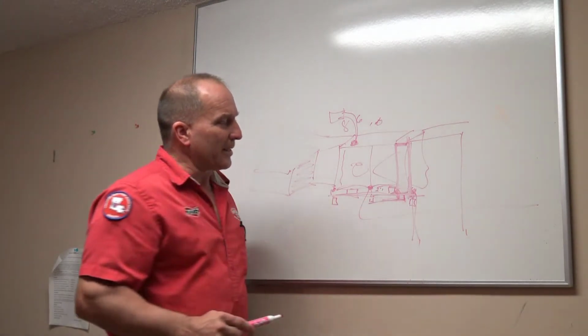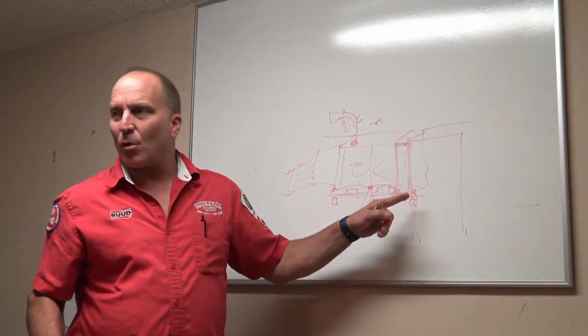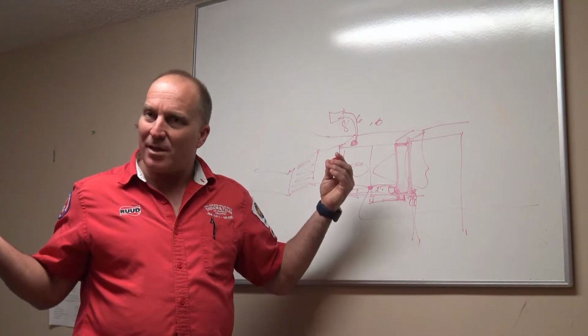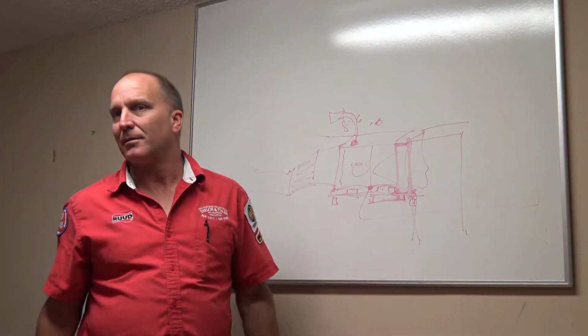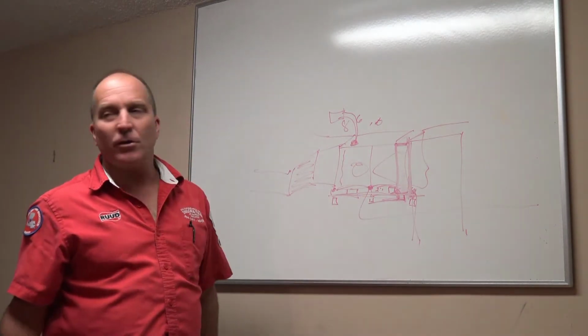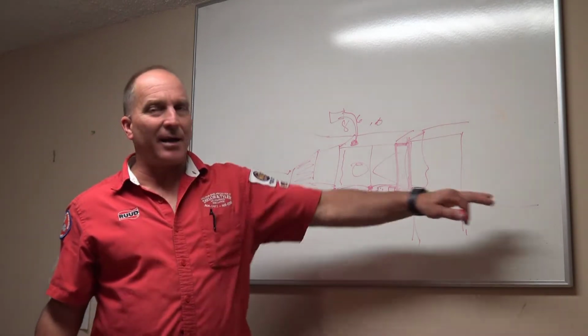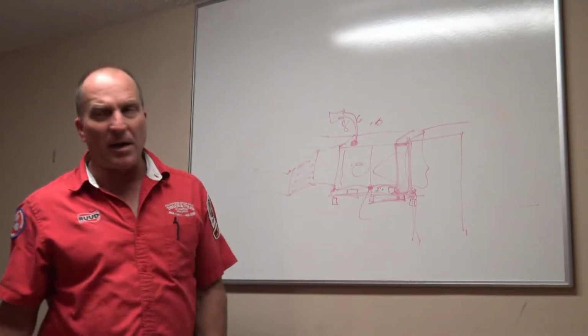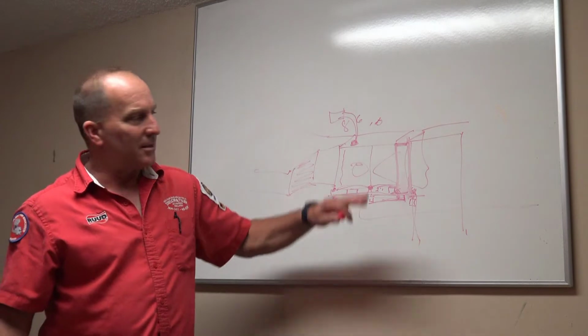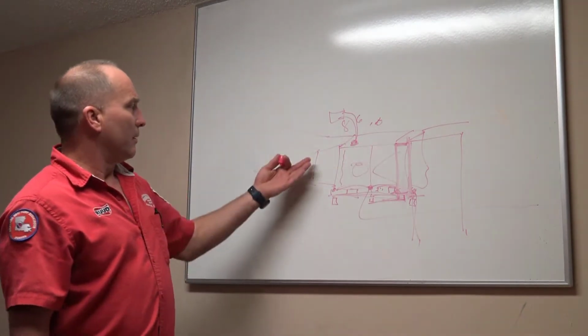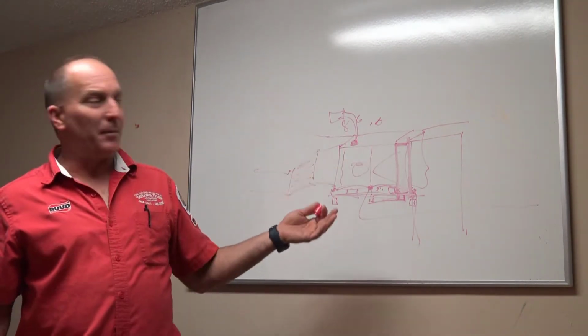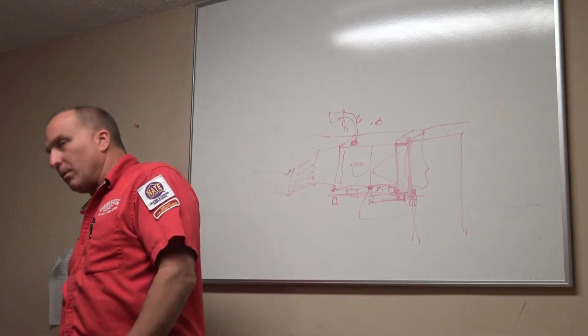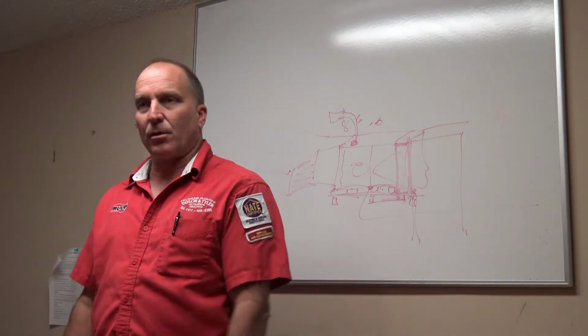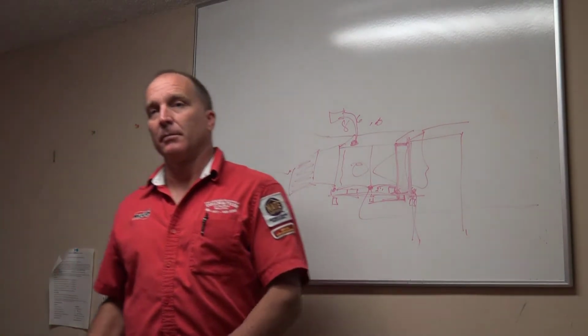So if there's no transition and the drain pan doesn't go all the way over to it, what is the condition of your air handler? It's poor. No downflow on your drain line. Drain line's not insulated. No float switches. Drain pan's rusted on the system. System is not raised at all. Plenum's kind of blocked out. I'm going to put condition poor. End story. And recommended and priced up.